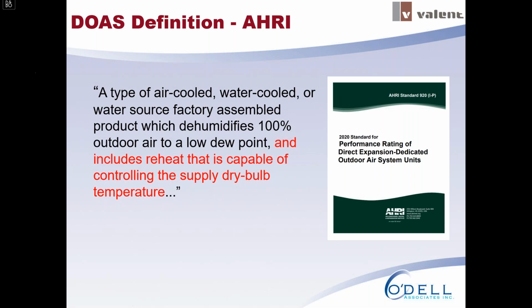Great, thanks, Nathan. So before we dive too deep, I want to start out with a definition of DOAS system, or dedicated outdoor air system. And AHRI has defined it as shown on your screen there. The key points are that DOAS units are really designed to dehumidify 100% outside air down to a low dew point. In addition, they also control the reheat, so that you're controlling the supply dry bulb temperature. So those two in tandem are really the key points of a DOAS system.